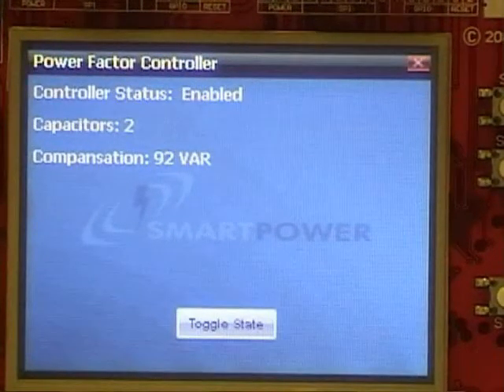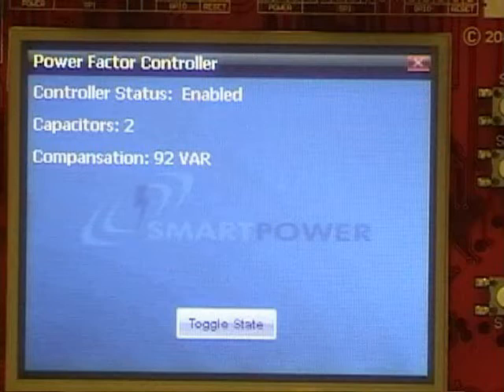Now the power factor controller window shows that two capacitors have been turned on. In our prototype we use capacitors which have equal ratings. This causes the changes to be in equal steps within a given tolerance level.